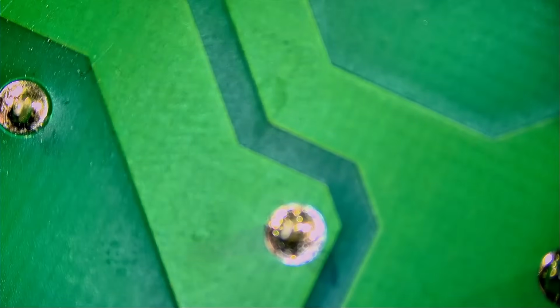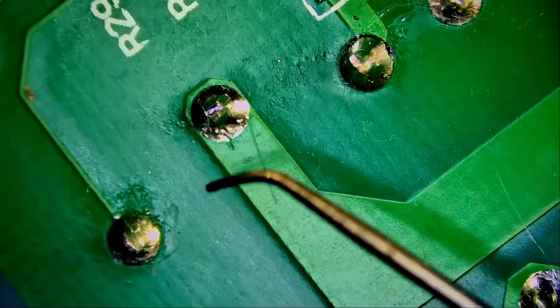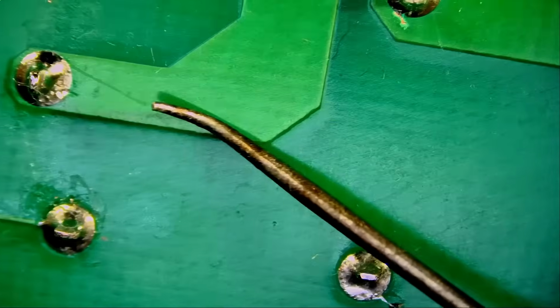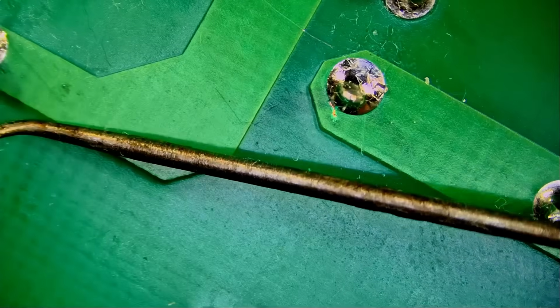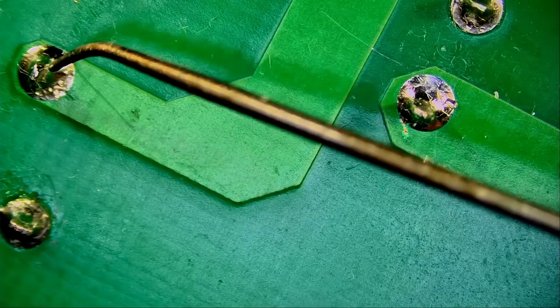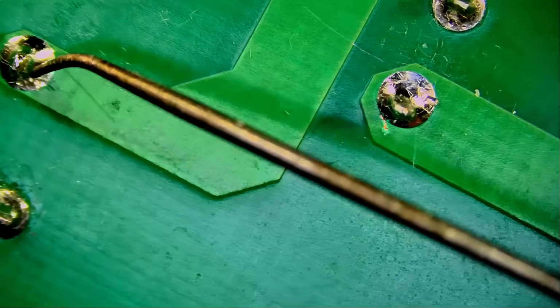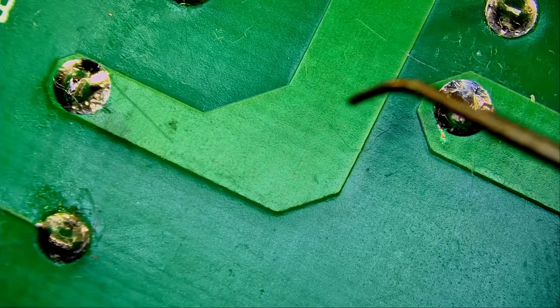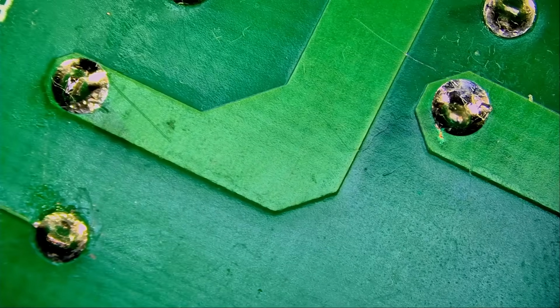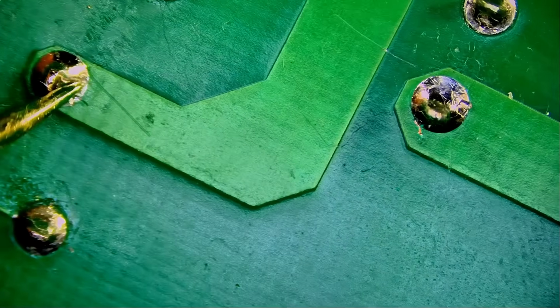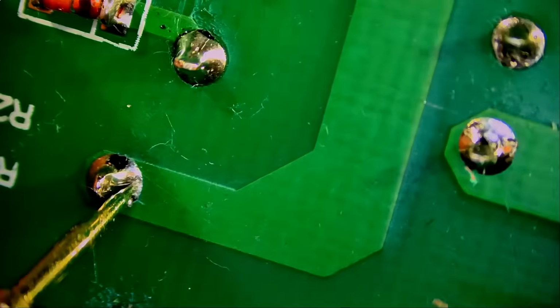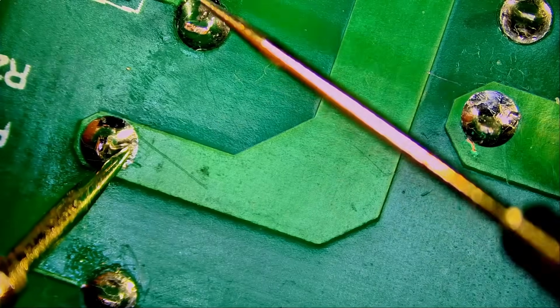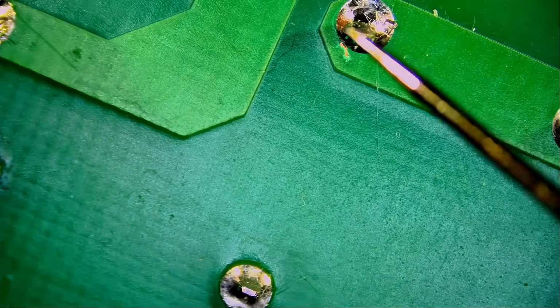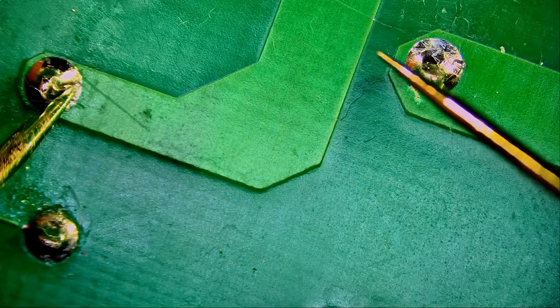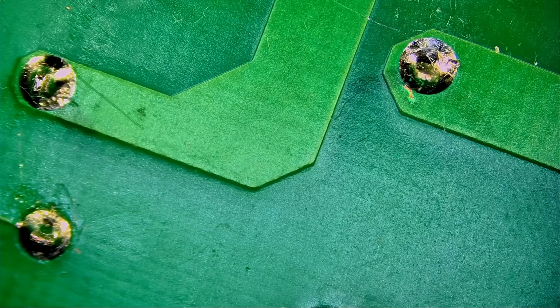And the relay is working. So what's happening is we are measuring if that line is switching over like this when we apply voltage, and that's why we get a beep when we measure from here to here. Right now if I measure from here to here, we get OL because it's disconnected. Let me show you, if you measure from here to here, good, from here to here, no. When we apply voltage, that line is going to switch over and we're going to have a continuous path from here to here. So we know all 3 relays are good.